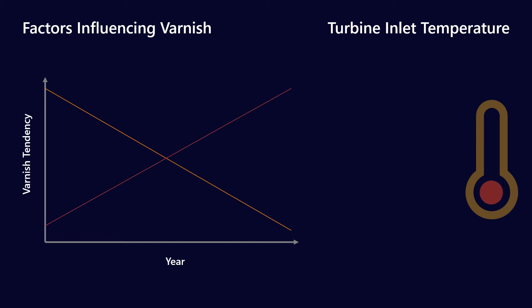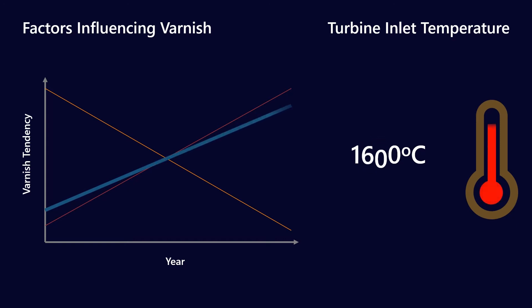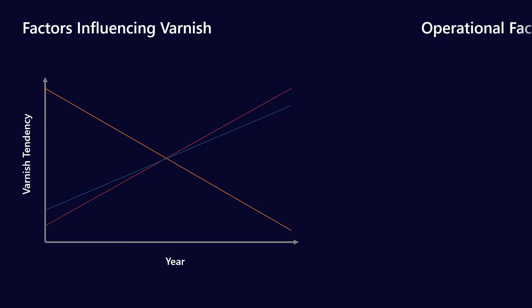The third factor is turbine inlet temperatures, which is obviously not controlled by lubricant manufacturers. Over the last few years, turbine inlet temperatures have been increasing from around 1,200 degrees Celsius to in the order of 1,600 degrees Celsius. That change is driven by turbine manufacturers wanting to increase thermal efficiency. The lubricant won't see 1,600°C directly, but as you increase the heat of the entire system, the temperature the lubricant sees will be higher, which accelerates the oxidation process and therefore the formation of varnish precursors.